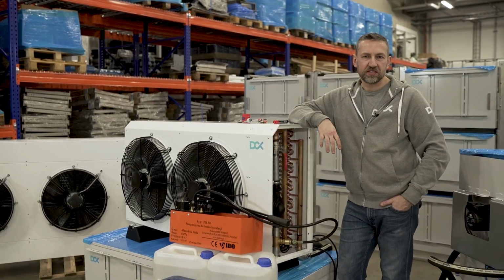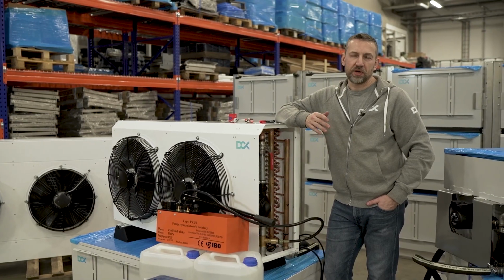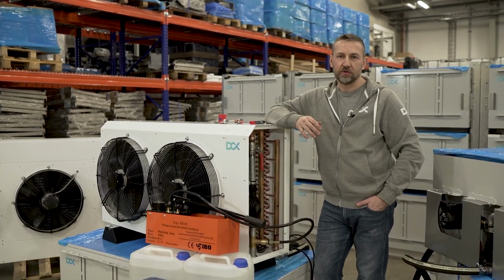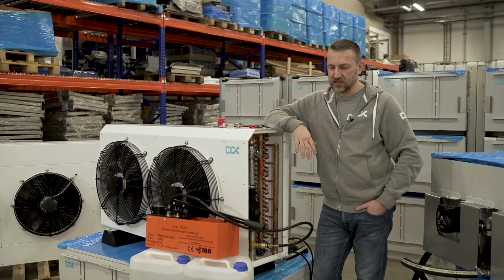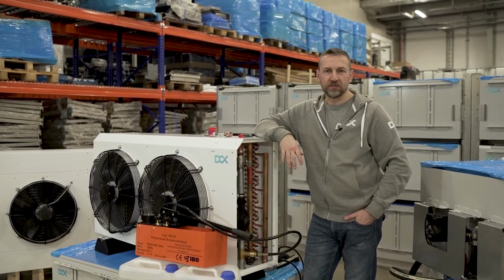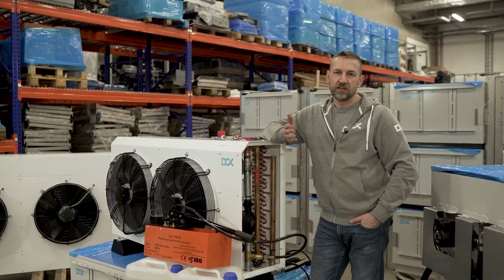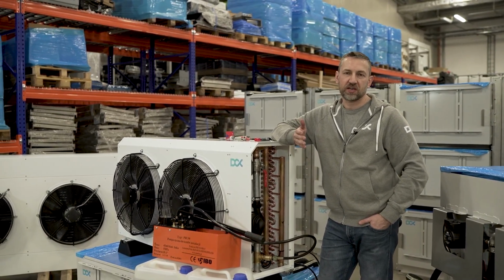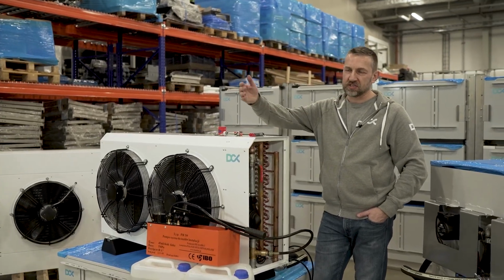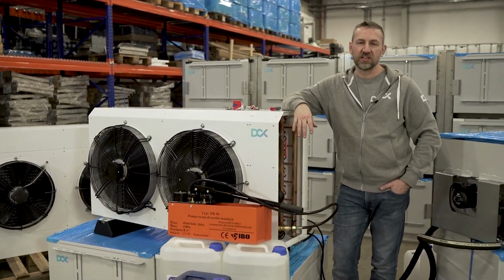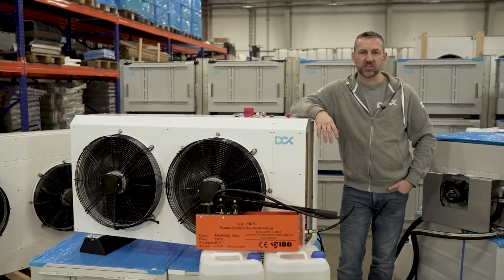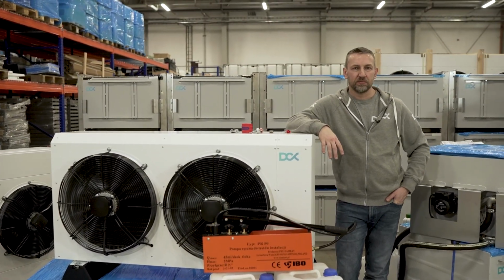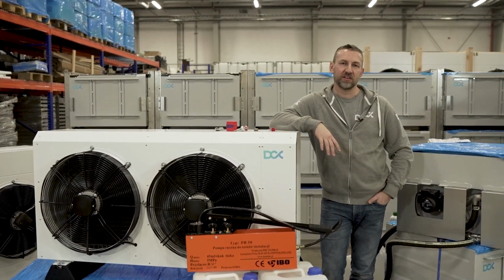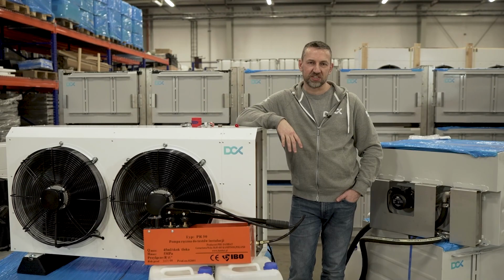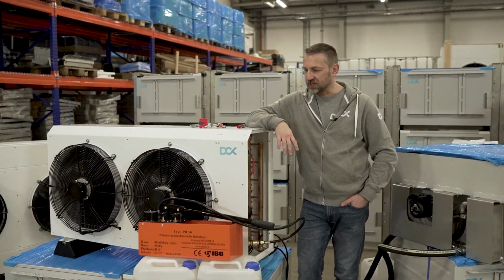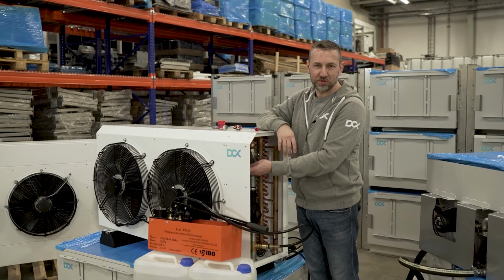So that's the noise of the fans at full speed. You need to remember we are in the silent warehouse right now. That's our shipping assembly warehouse, and that's the full speed of the fans. Normally, if you have 50 or 60 decibels outside, located in a typical city area, that will be just like an additional AC unit, maybe a little bit louder. That's designed for removing 40 kilowatts of heat from your system, so it must be noisy, and that's the least noise you can get. Shipped to your door.